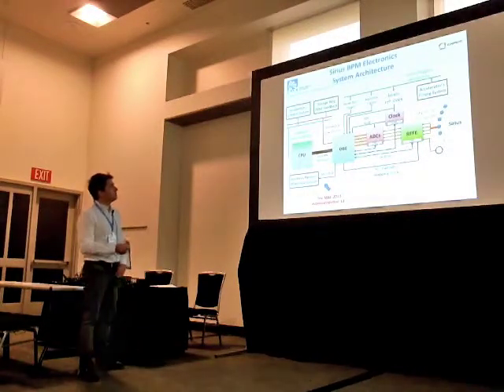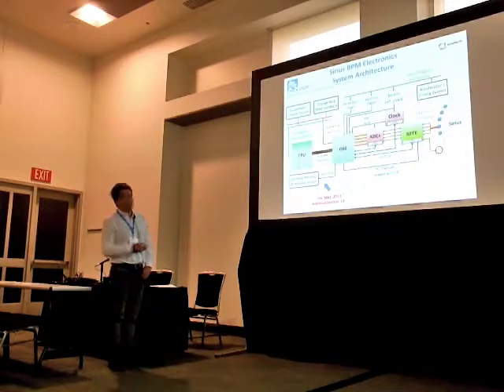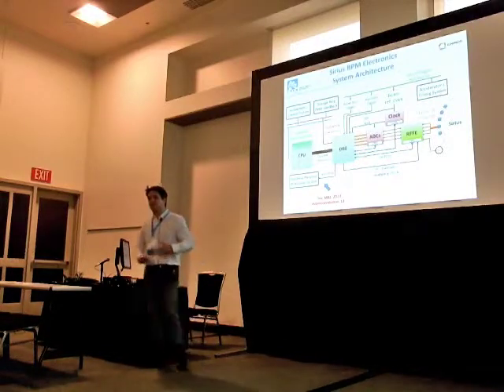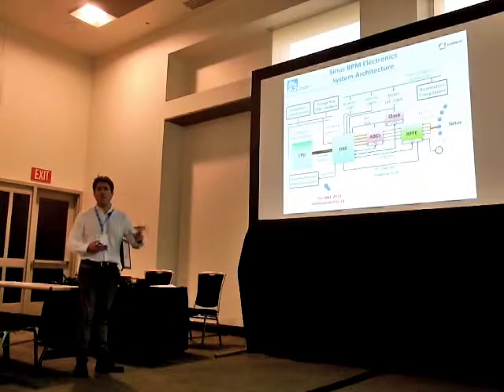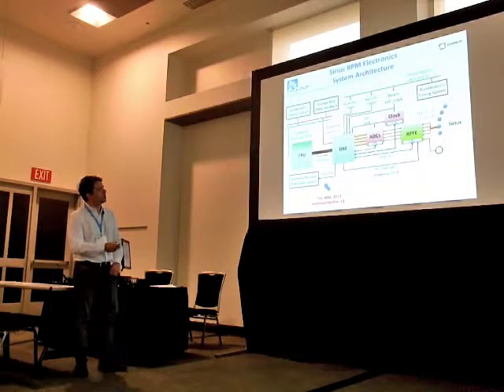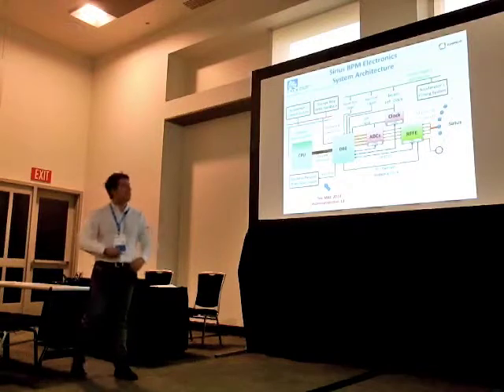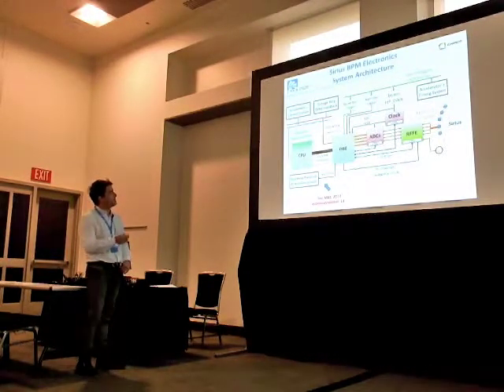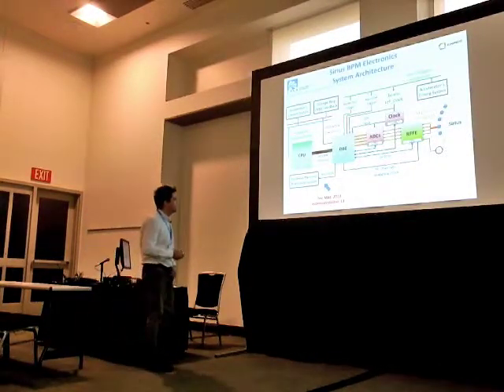So as I said, for Sirius, we are working on an in-house solution, and I think that it's in the blood of most of our engineers to start doing in-house solutions. Whenever they find a problem like that, basically you have on Sirius several beam positioning monitors. You have to convert radio frequency: the electron passes through antennas and generates radio frequency. We have to convert it to digital information, put it in a feedback system in a matrix that recalculates and returns to the correction system of the orbit.